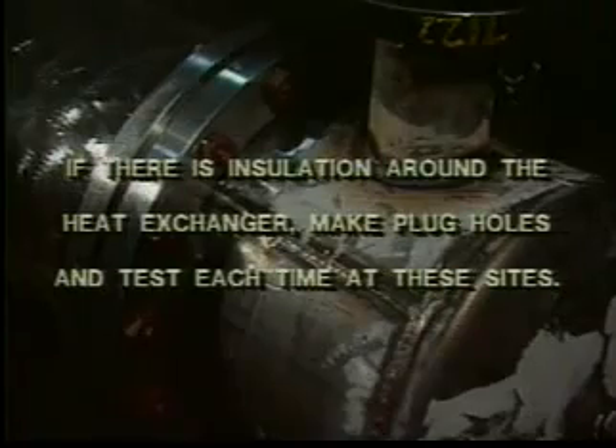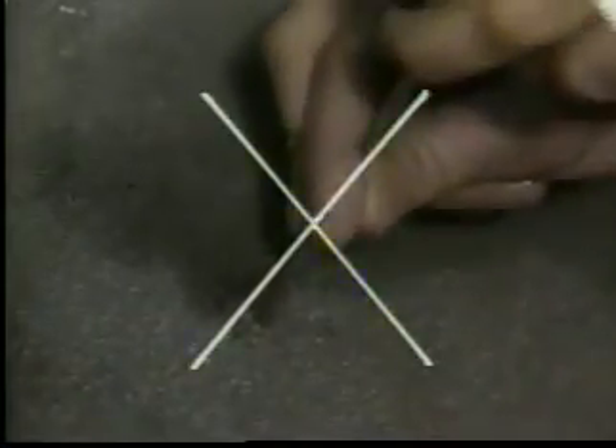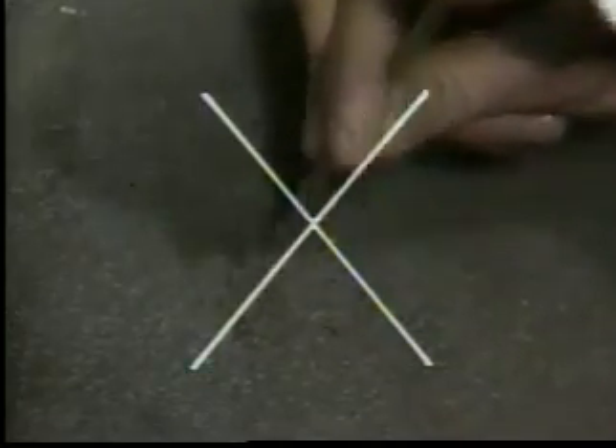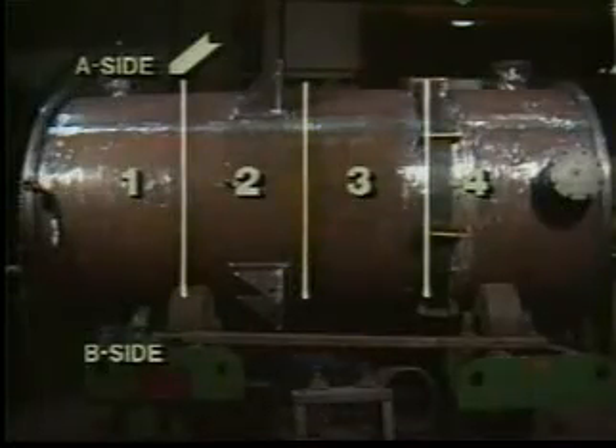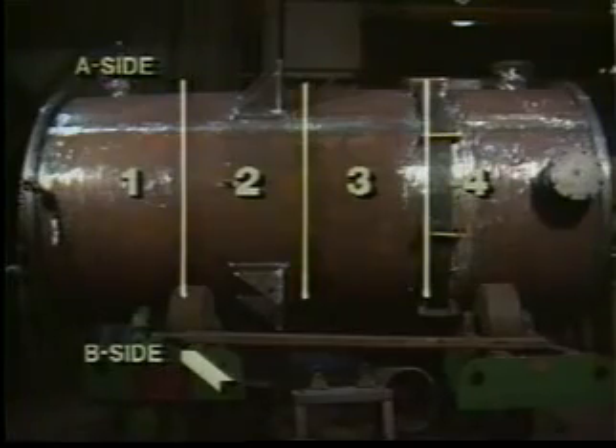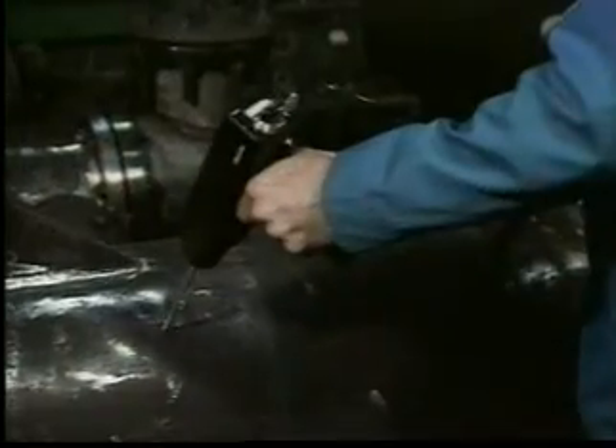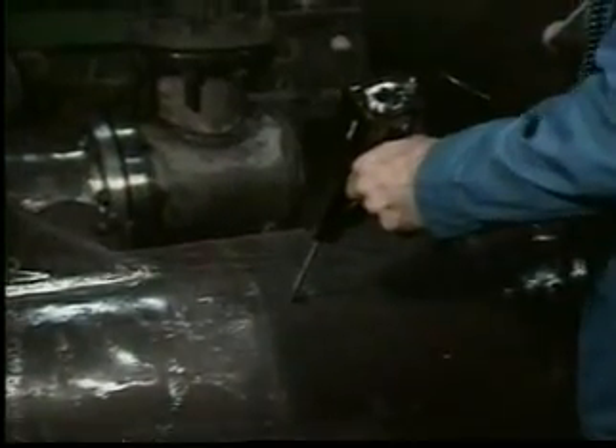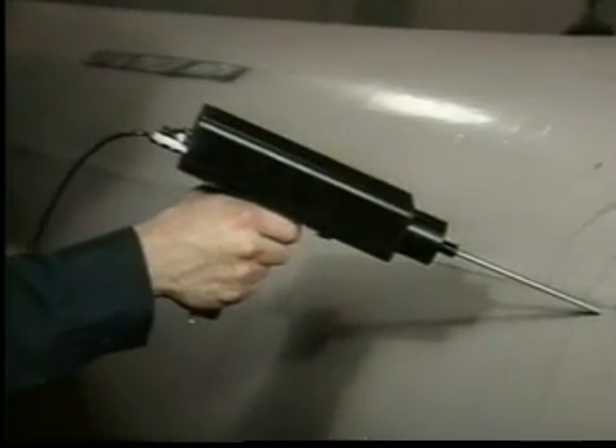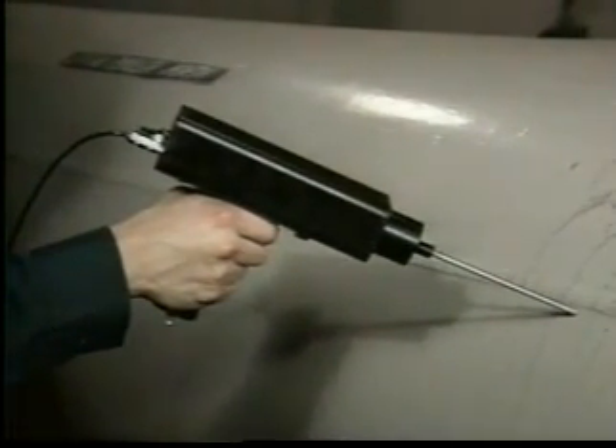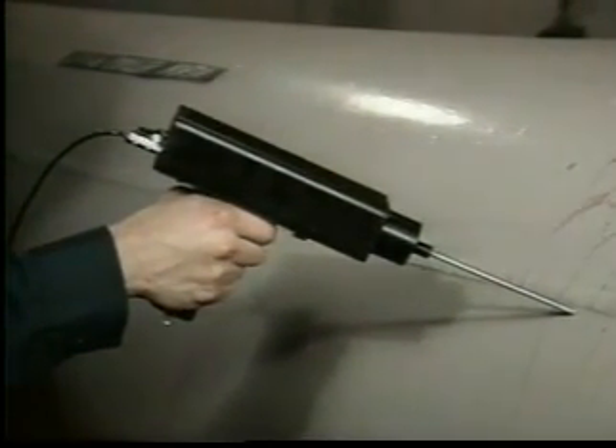If there is insulation around the heat exchanger, make plug holes and test each time at these sites. Never use the contact probe to create a hole. The pressure will damage the transducer. Check four test locations on one side, then four locations on the other side. This method is effective for ongoing monitoring of gross tube leakage. Small leaks in peripheral tubes or gross leakage in central tubes can be detected.